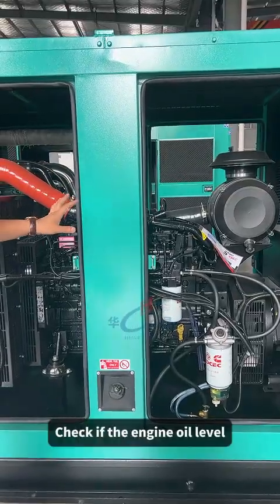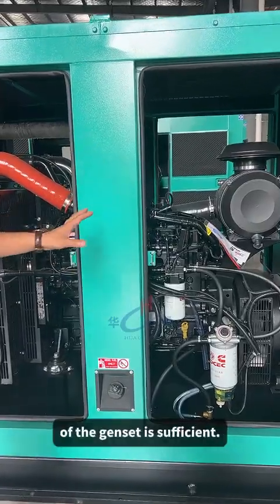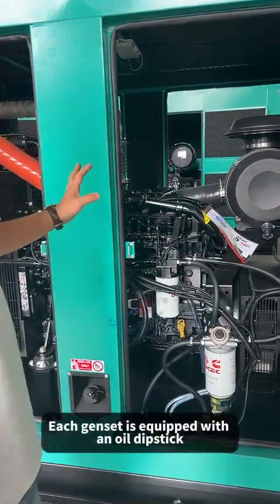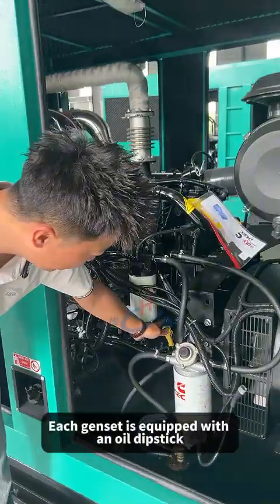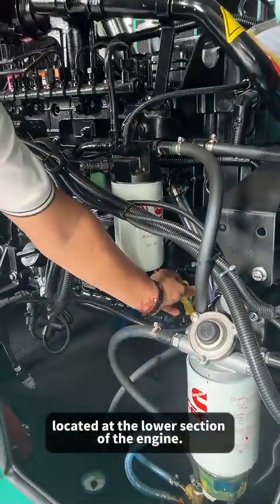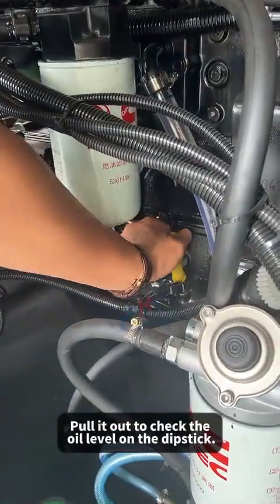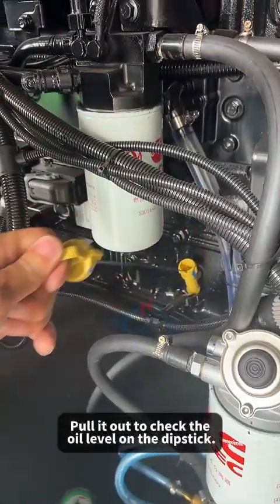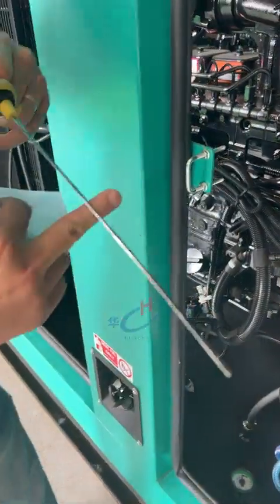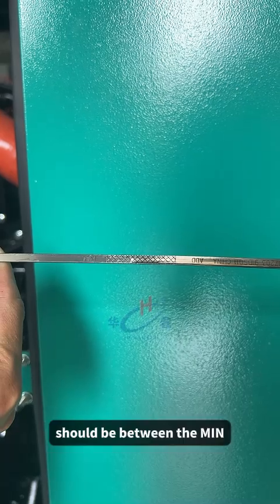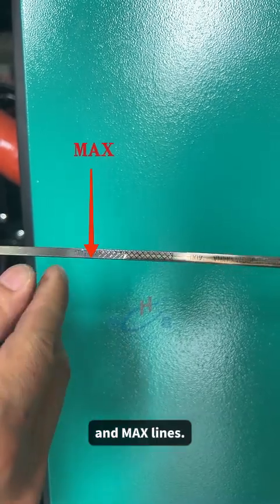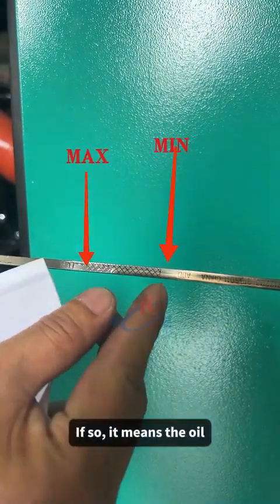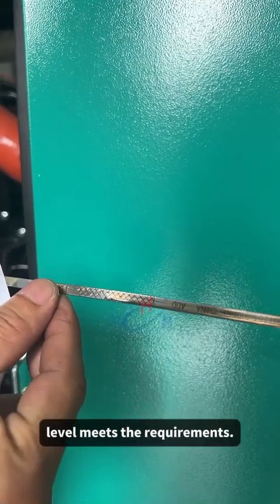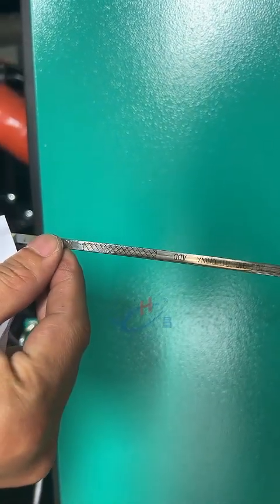Step 1. Check if the engine oil level of the genset is sufficient. Each genset is equipped with an oil dipstick located at the lower section of the engine. Pull it out to check the oil level on the dipstick. The oil level should be between the min and max lines. If so, it means the oil level meets the requirements.